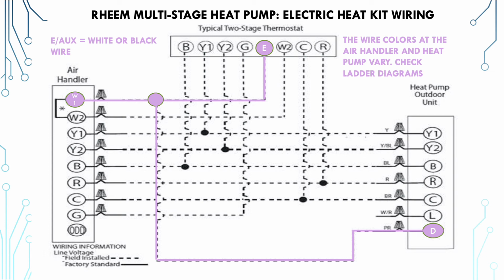Okay, so this is basically one stage of electric heat. The wire is going to be whatever color you use. You can use the white wire because it might be white. I would have colored this white, but you wouldn't be able to see it. So in this case, I made it purple, but you have that unused white wire, or you could use a black wire. Generally, if you have a white and black wire, you typically would put white on your first stage, which is going to be your E, or it might say E-aux, EMER, X. Now be careful with the X, read the manual for that particular thermostat, because sometimes that might mean electric heat, or X might mean something entirely different. It might be a sensor contact or something.